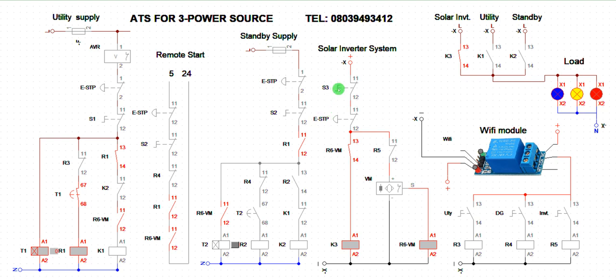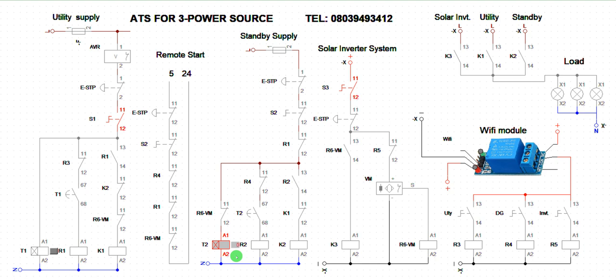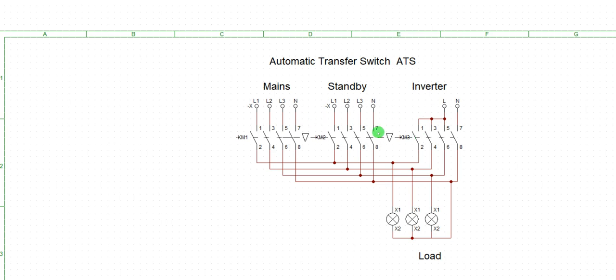Let me demonstrate: I'll knock off solar. You can see this contactor now closes — that's utility. Now I'll knock off utility too. Watch the genset come up — it will crank, start, and stabilize. When the speed stabilizes, the contactor closes and gives output K2. Here's the power circuit: the mains/utility, the standby genset, and the inverter system, with single-phase and three-phase connection options shown.